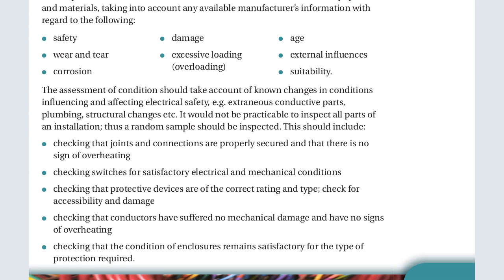Most of them, you'll find, have metallic parts that can get connected to electricity in case of a leakage or in case of a fault. So all these are called the extraneous parts, the extraneous conductive parts, and they need to be bonded. Bonded means connecting all of them to the main earthing system.